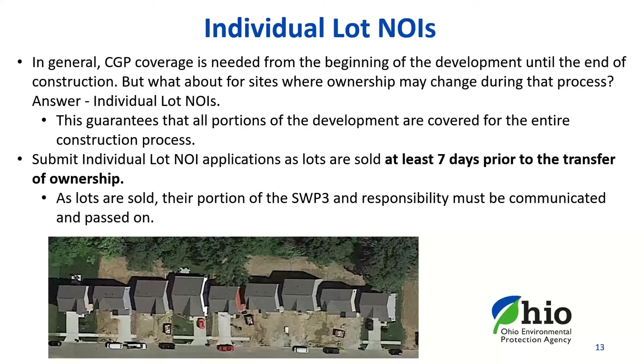Let's take a look at an example of a subdivision of when to apply for or transfer coverage depending on who you are. If you're the developer, but you're not going to be building any of the homes, you're going to need to obtain general permit coverage to start construction. And you're going to want to hold on to it until one of two things. The first is that every single lot has applied for and gotten an individual lot NOI approved, which means their coverage has been transferred to them. However, the caveat is that if you have put in centralized controls that serve multiple different lots, say like a sediment basin, you're going to need to keep your coverage because you're responsible for those centralized controls during the entire active construction sequence.